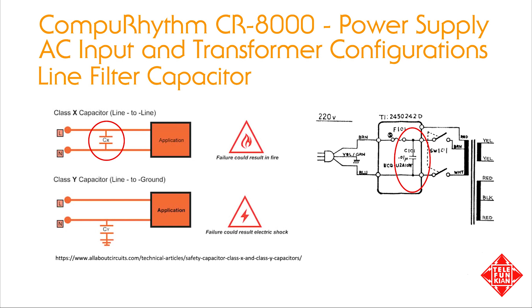We'll be replacing C101 with a more modern X2Y2 safety-rated capacitor. Safety capacitors are manufactured so that they're guaranteed not to fail short, unlike the capacitor currently in the instrument, which does have that potential.